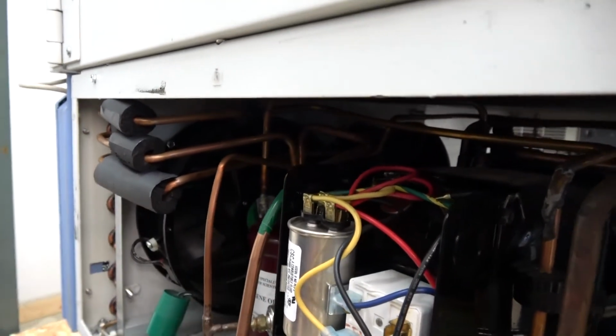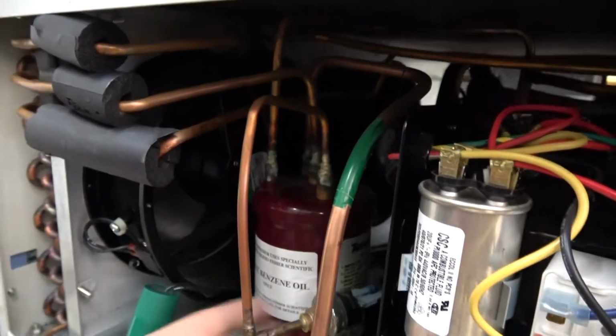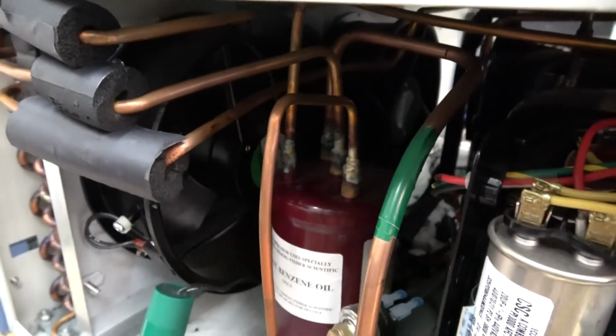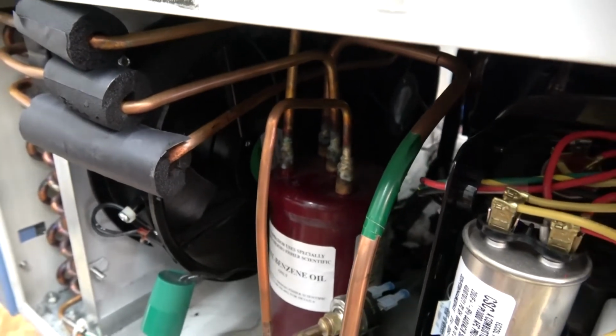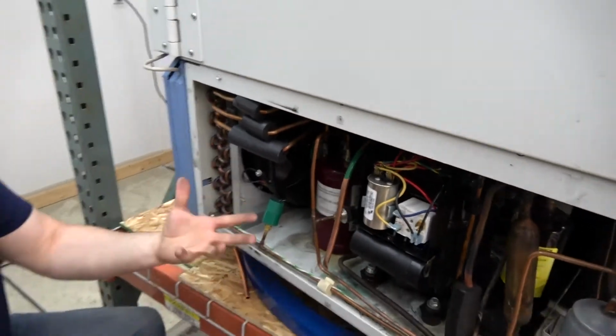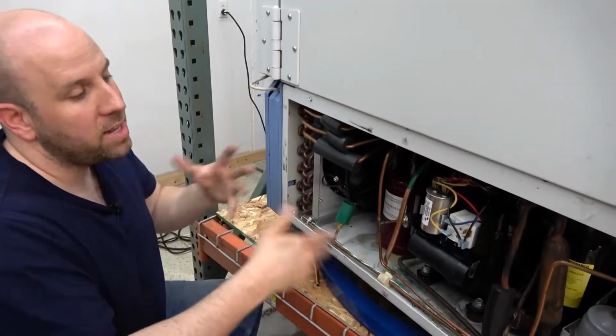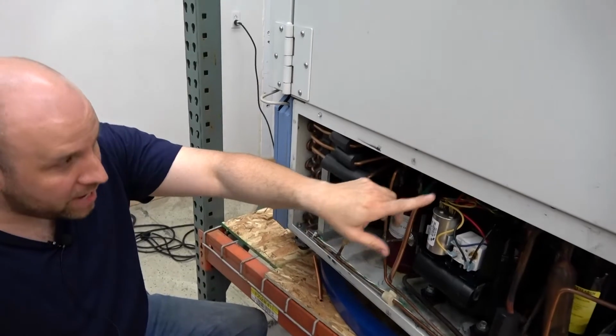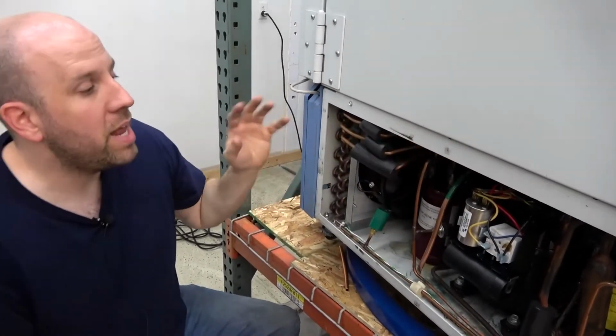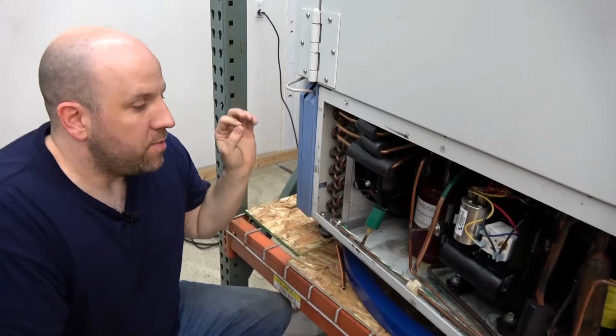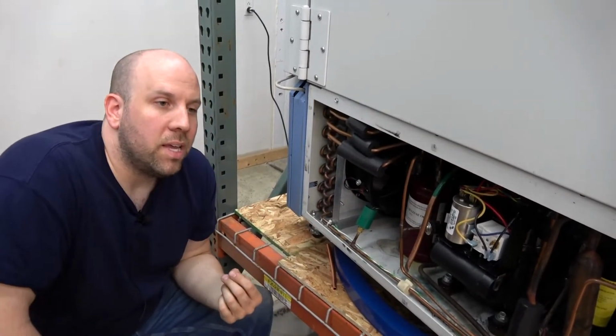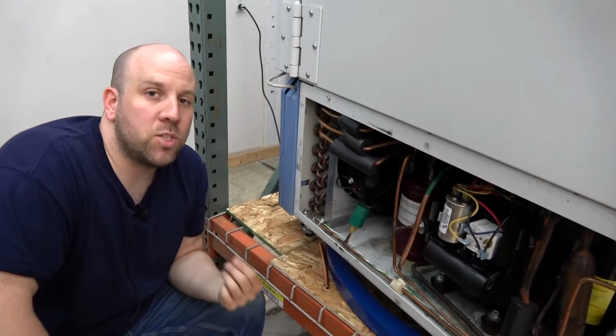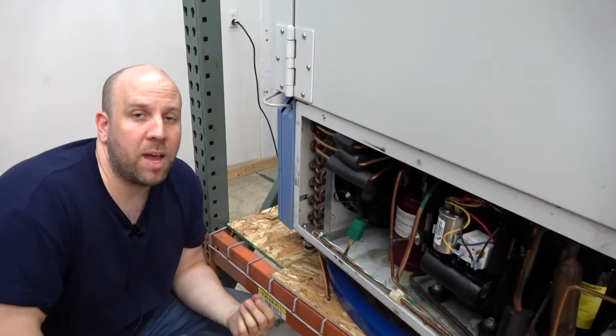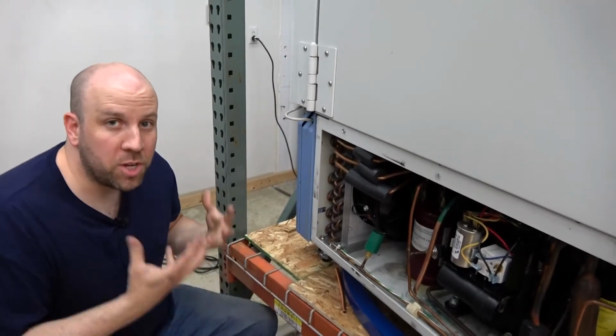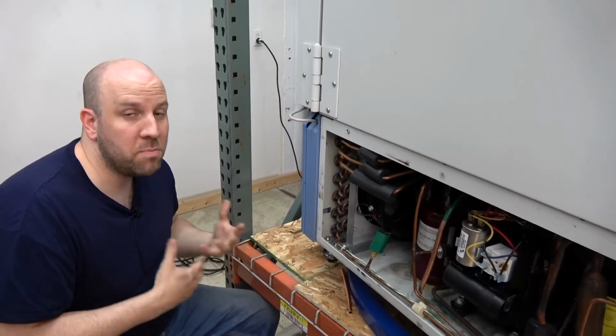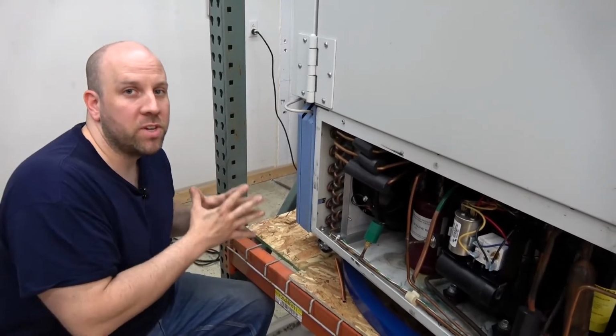It comes out and it goes into this oil separator that wasn't on the first stage. So this component actually separates the oil, which intrinsically is part of the design. It gets sucked in through the refrigerant in the system and it passes through. So when that refrigerant gas comes through, it has oil in it. So this component filters out the oil, which is important because the less oil you have in your refrigerant when it's going to do its job up there and evaporate, the more actual refrigerant you can fit in the lines. Because if the refrigerant's mixed in with a bunch of oil, you're not getting as much refrigerant in the line.